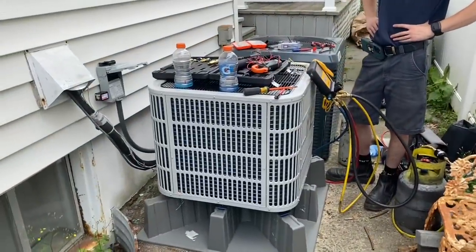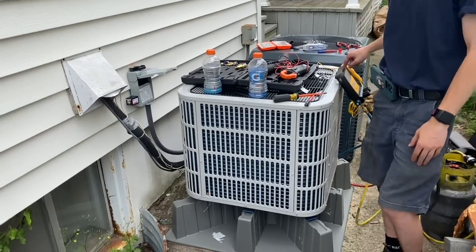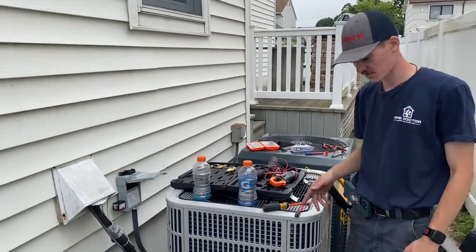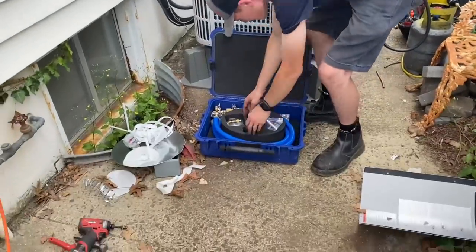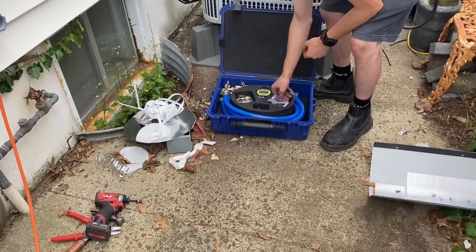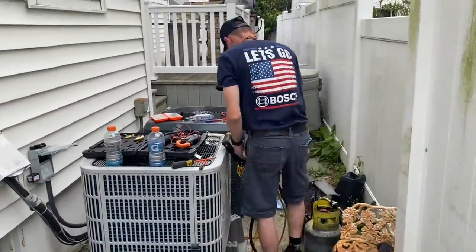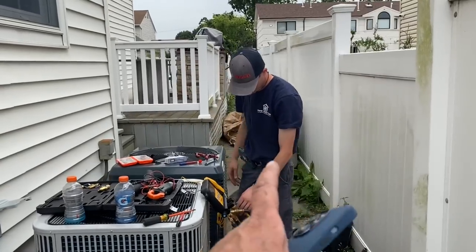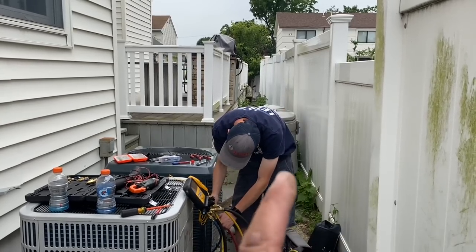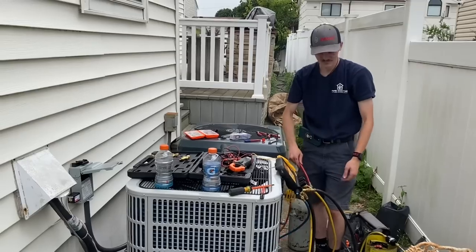She's holding good — we can start vacuuming down. The beautiful Bosch. The test mode on this pressure test actually takes into account the temperature of the pipe, so it actually knows if you're really losing pressure based on temperature differences. Very nice. For evacuation and vacuum purposes we're using the Eco Tools True Blue professional kit. Ladies and gentlemen, if you'd like a Mikey Pipes Bosch Summer 2022 t-shirt, we have them available in medium, large, a couple extra-larges, 2X, and 3X — a donation of $23 is appreciated and I'll mail it out anywhere in the United States. Email me at mike@mikeypipes.com.